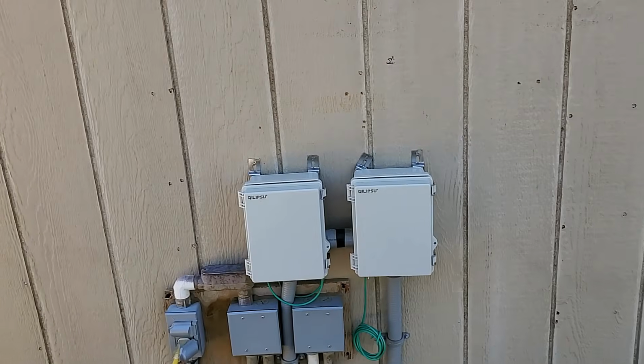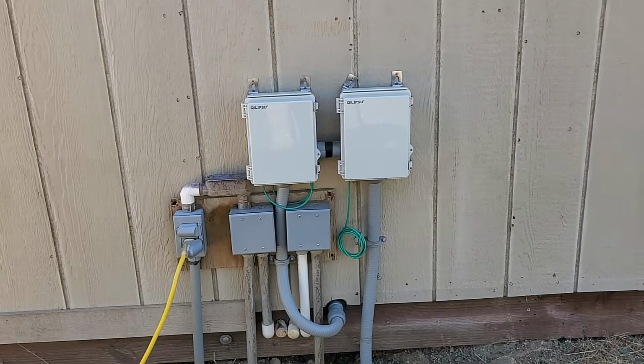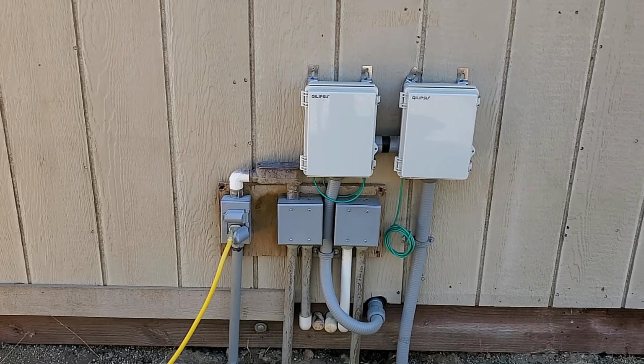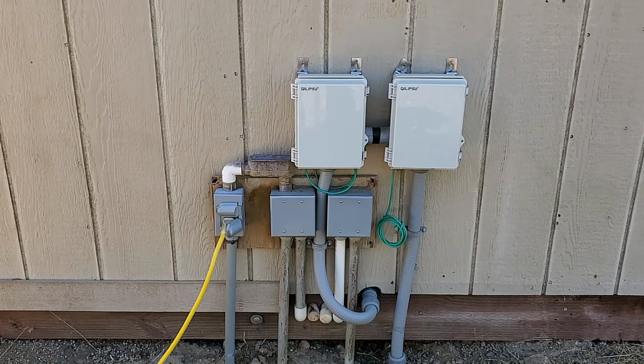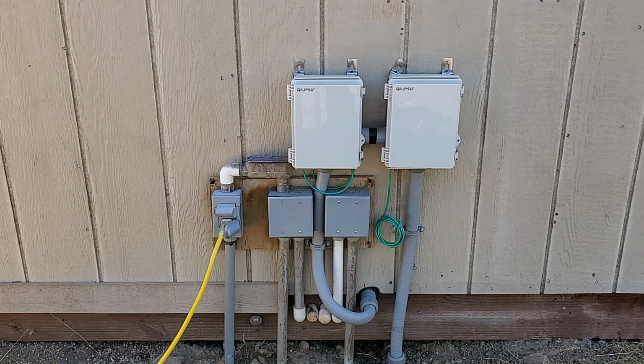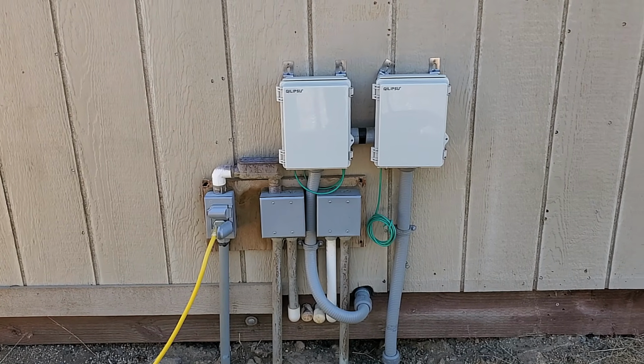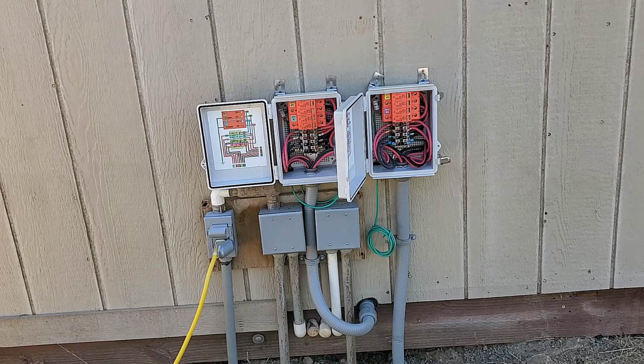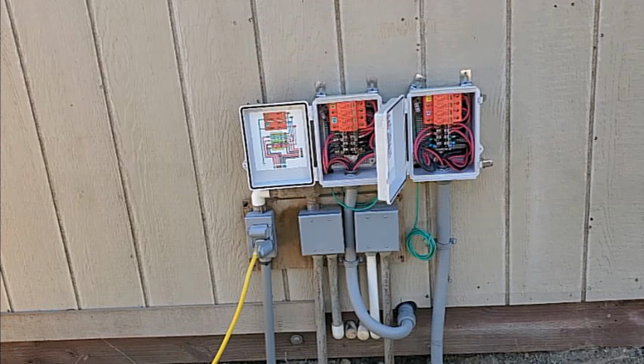A couple of years ago, while I was installing the new well and preparing to bring the solar system online, with inverters, batteries, and panels freshly delivered, I had already chosen this location for what would become the solar field. Knowing that, I ran 4 pairs of 10-gauge photovoltaic wire in conduit from this site directly to the inverter system located in the garage. Later, when I installed the solar arrays, I also enclosed 4 additional wire pairs in conduit leading from the array structure itself to this central PV connection station.